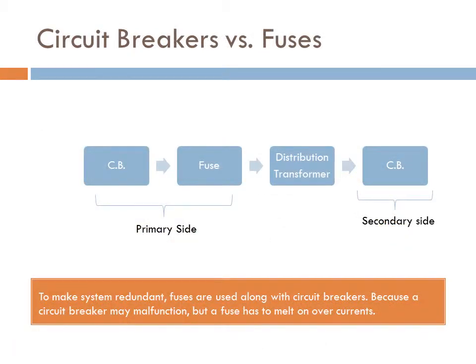As we have seen that circuit breakers are more redundant. So to make system redundant, fuses are used along with circuit breakers. Because circuit breaker may malfunction, but a fuse has to melt on over current. In a distribution transformer, circuit breaker and fuse are connected in series on a primary side, while on the secondary side only a circuit breaker is connected. So that in the case of any failure, if circuit breaker does not work, fuse breaks the circuit.